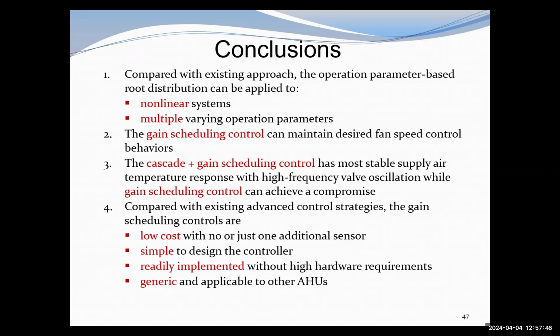And the gain scheduling fan speed control can maintain desired fan speed control behaviors and achieve approximately identical control performance under all operation conditions. For the cooling coil valve controls, the cascade plus gain scheduling control has the most stable supply air temperature response. However, it will have a high frequency valve oscillation, while the gain scheduling control can achieve a compromise between the two.